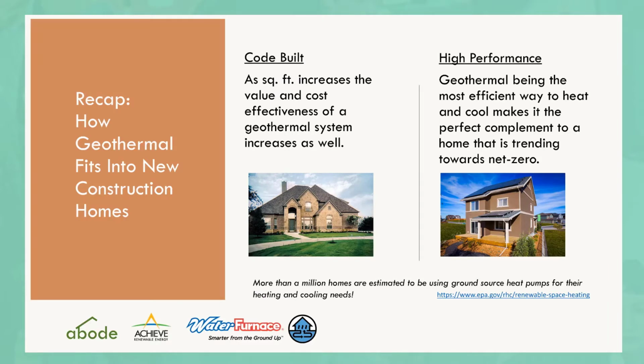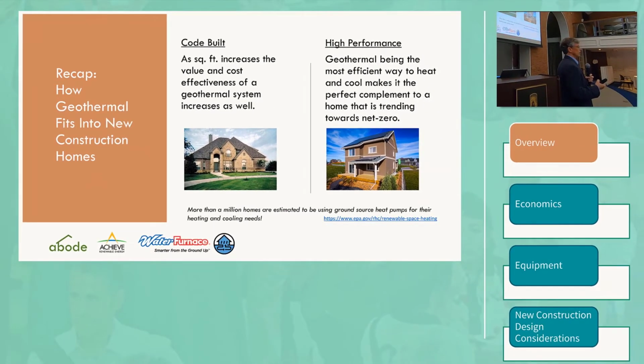There are economies of scale with geothermal installations on the residential side. This is primarily because ground source heat pumps are expensive compared to other heating devices. And if you're going to heat a house, you need at least one. And that first heat pump costs you a chunk of money. If it's the smallest size in its model line, you're still paying a decent amount of money for that heat pump. But then jumping up sizes, say from a 2 to a 3 to a 4 or even up to a 6-ton capacity unit, those changes in capacity have only small incremental changes in cost. So it's absolutely not the case that a 3-ton heat pump costs half as much as a 6-ton heat pump. It probably costs 85% the cost of a larger unit.